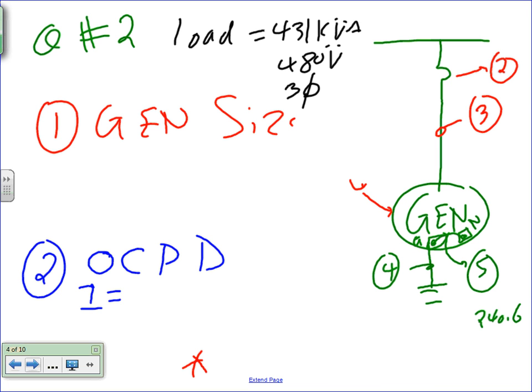So let's use green. I need to size the following for this. Number one is the gen size. Number two is the overcurrent protection device for the gen. Number three is the conductor that feeds to the gen. Number four is the grounding electrode conductor for the gen. And number five is the main bonding jumper for a separately derived system generator. Everybody can see, guys, here's a grounding here. There's the neutral, and I bond them as a separately derived system. Typically, I need to size five things for this generator.